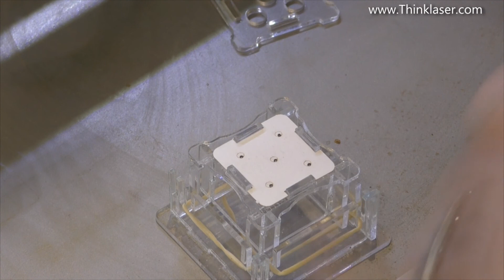This is the final test because we don't want the beam to clip the edge of that orifice, otherwise we should be losing power. And it does look as though the beam is sitting down here at about 6 o'clock. So we could really do with trying to tweak that beam up to a slightly different position. Now we know that they're all in the same position, so we don't have to go around and check every other position. We don't have to check all the positions again. So all we need to do is just check it in one position.